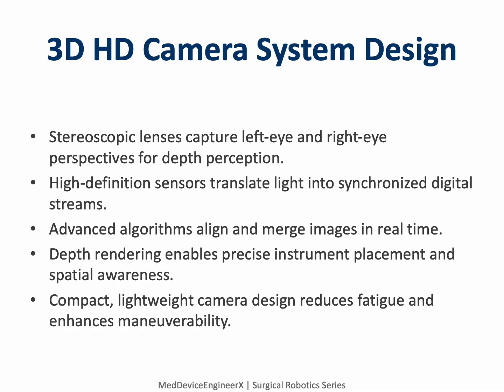The 3D HD camera is where perception becomes precision. Using dual optical channels, the system captures slightly offset images, one for each eye, creating a stereoscopic effect once processed. Inside the camera, high-definition sensors convert photons into digital signals, which are synchronized and merged by real-time algorithms within the tower. The result is true depth perception, allowing surgeons to judge distances and tissue planes with natural accuracy.